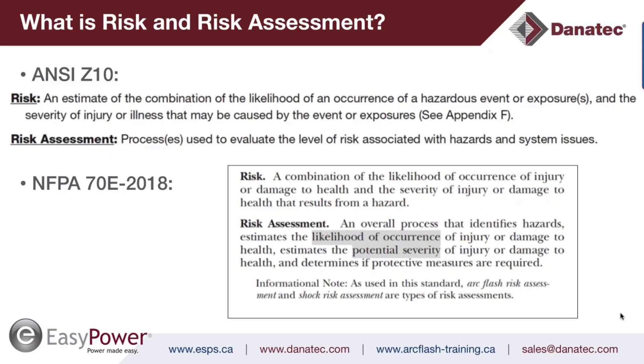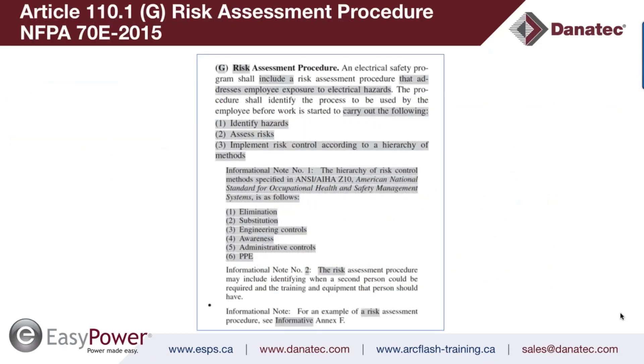The overall risk assessment procedure is a separate process from the arc flash risk assessment and the shock risk assessment. Those two assessments feed additional protective measures into the overall risk assessment procedure to reduce the inherent or initial risk level to a residual risk level that is as low as reasonably practicable — but only from the perspective of potential injury or damage to health. For instance, arc flash PPE drives down the inherent potential injury from third-degree burn to the 50% probability of onset of a second-degree burn.